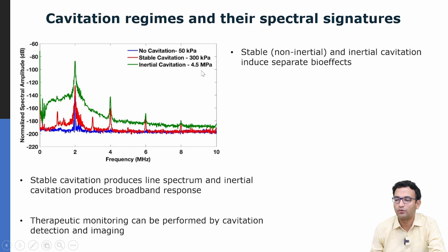And then as you go to much higher pressures, 4.5 megapascal, you see that the line spectrum becomes very weak, and primarily you get a broadband signal increase, which is because of impulsive bubble collapse, which is characteristic of inertial cavitation. So, now this is a very exciting development, because just by listening to the bubble activity, we can say whether primarily stable cavitation is going on or inertial cavitation is going on or both, and this listening can be performed by a cavitation detector, which is another piezoelectric transducer which is listening to the signals coming from these cavitating bubbles. It is only listening but not sending any pulses, that is why the word passive. So, a passive cavitation detector can actually tell you what kind of bubble activity is going on.